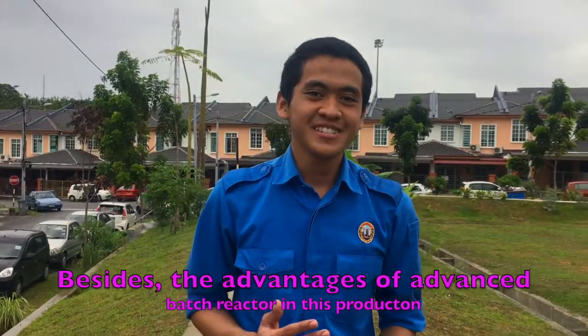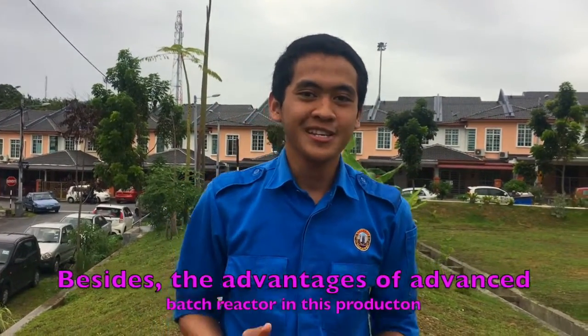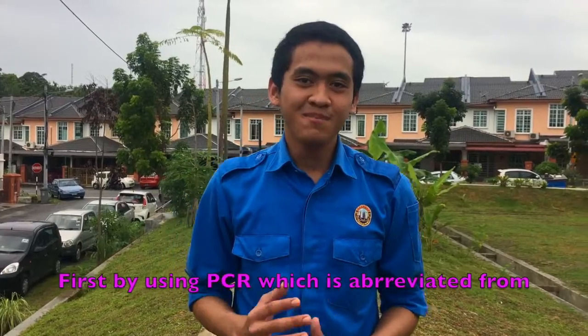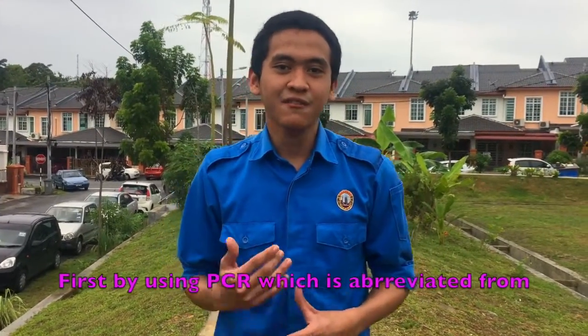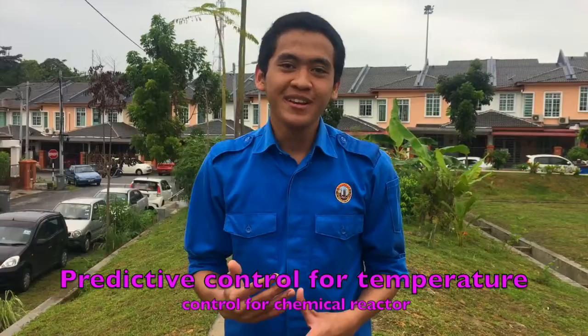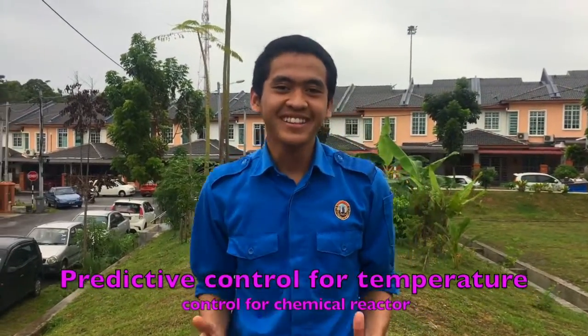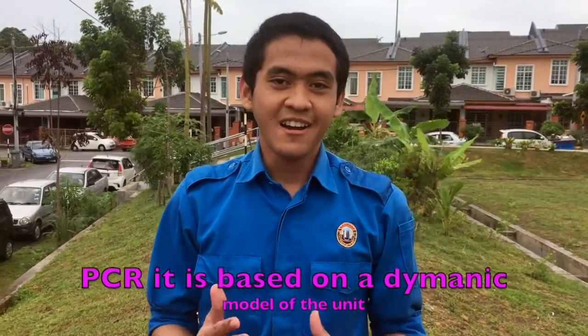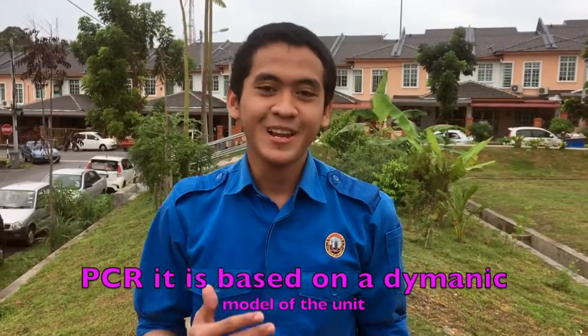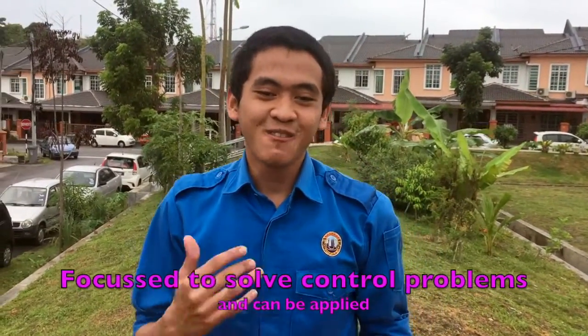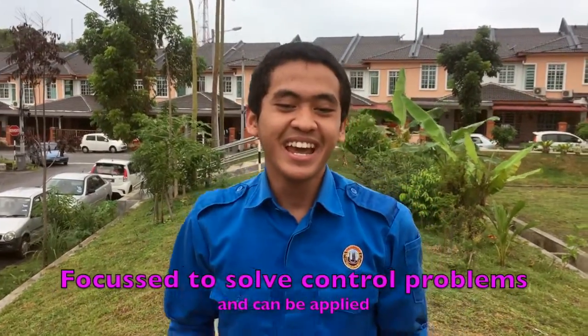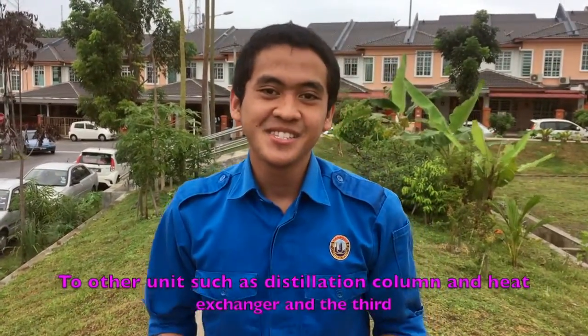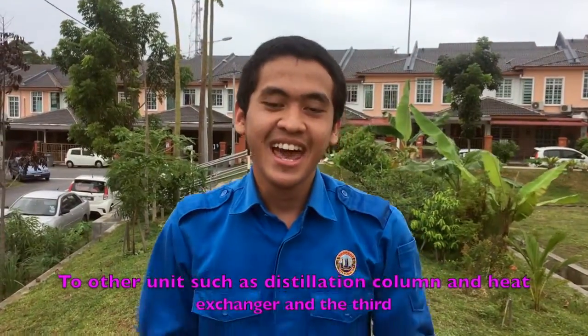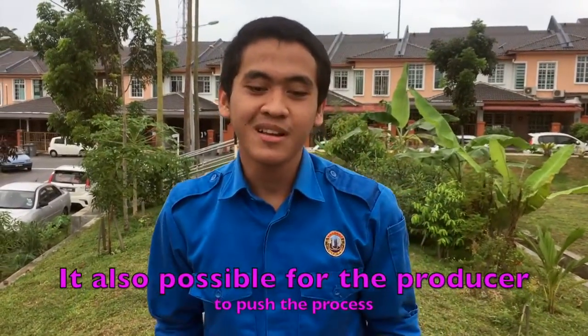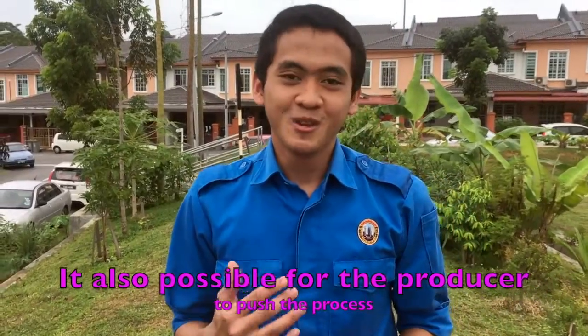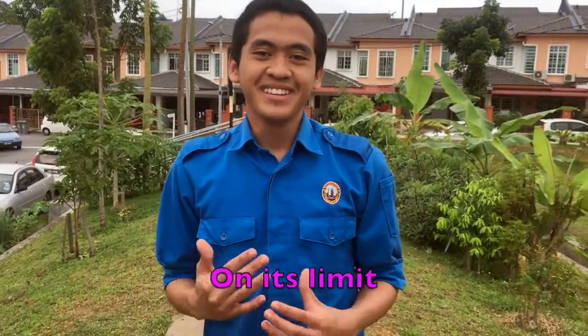Besides the advantages of the advanced batch reactor in this production, first, by using PCR, which is abbreviated for predictive control for temperature control of the chemical reactor. PCR is based on a dynamic model of the unit, focused on solving control problems, and can be applied to other units such as distillation columns and heat exchangers. And third, it also makes it possible for the producer to push the process to its limit.